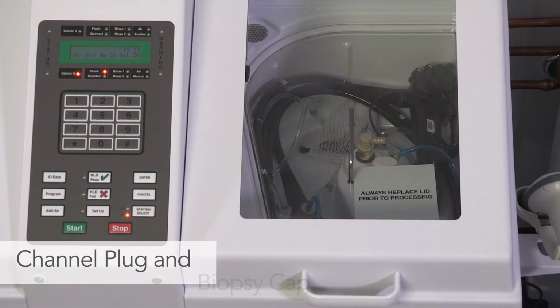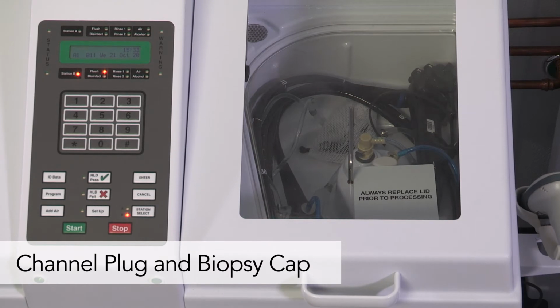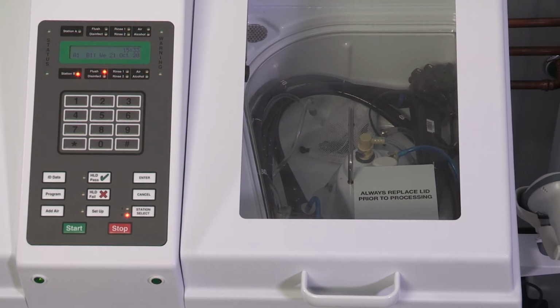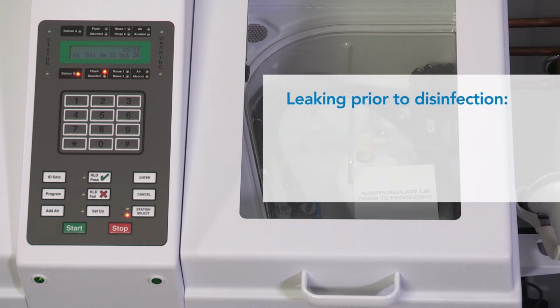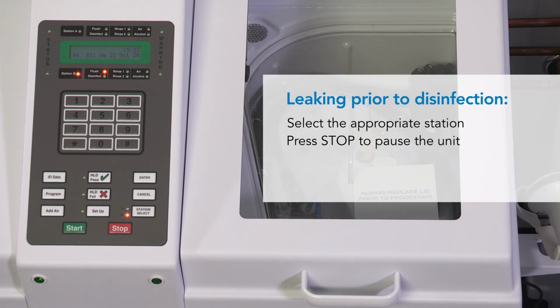During the cycle, the channel plug in the control section and the biopsy cap are designed to permit the passage of small amounts of fluid. No other connections should leak. If leaking is detected, it is usually a sign of a bad or loose connection. If prior to disinfection, select the appropriate station. Press Stop to pause the unit, correct the problem, or replace the hookup.